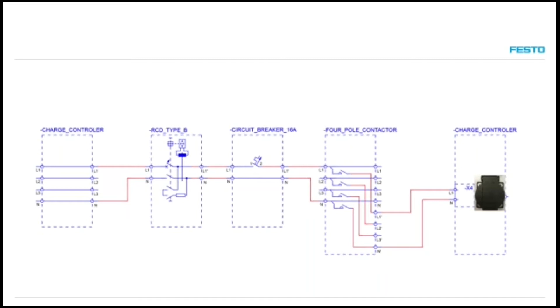From the charge controller module, we use only 2 lines out since this is single phase charging: line 1 and neutral, going to our single phase RCD ground fault protection device, then to the circuit breaker, then to 2 lines of the 4-pole contactor, and back to the charge controller, to the plug of the charge controller.